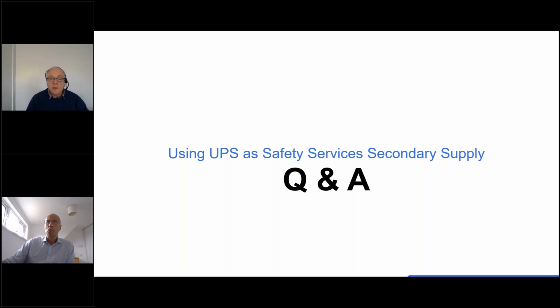Thank you. Is there a requirement for a battery room to be kept separate from the UPS if kept in separate racks? Are battery rooms to be fire rated? Yeah, if it's for life safety, all of it has to be able to withstand the fire for the required period of time. It's often good to put batteries in a separate room, in a separate environment, because the UPS needs an environment that is clean and dust free, but it has a variable temperature range, maybe 0 to 40, as long as it's clean and dry, whereas the battery needs to be kept at 20 degrees. So if it's a large battery, we can partition that room off and just condition it to keep it at 20 degrees, and that is quite often a good way of doing it. But it does need to be fire rated if it's a life safety system.